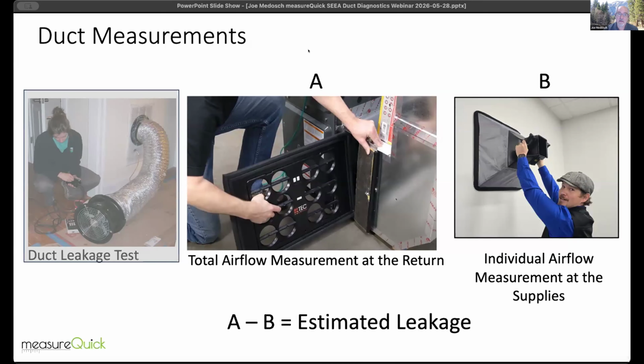I can kind of estimate that, do I have a lot of leakage? And if I know where my ducts are, then it would be leakage outside. So there are a lot of ways now to confirm what my issues and challenges are between airflow and duct supplying back into the house. So there's a lot of great training out there on this kind of stuff. NCI is a number one source for using these kinds of methods and promotes this regularly.